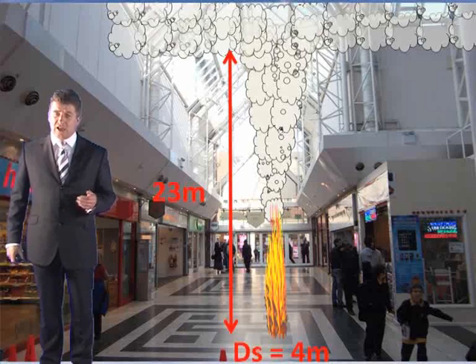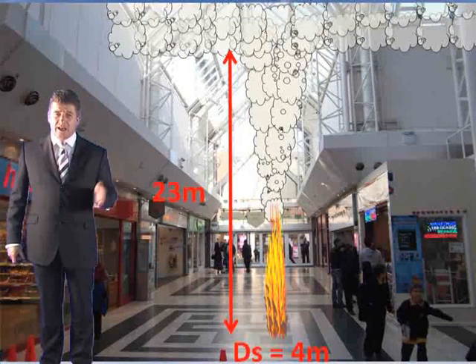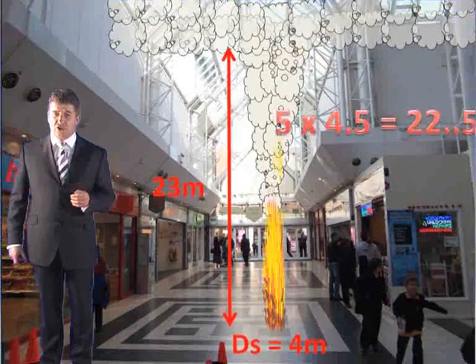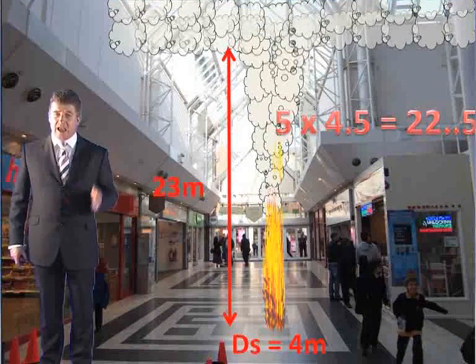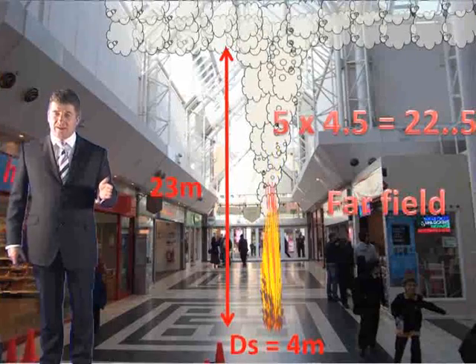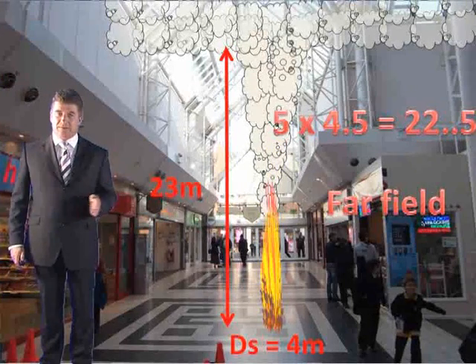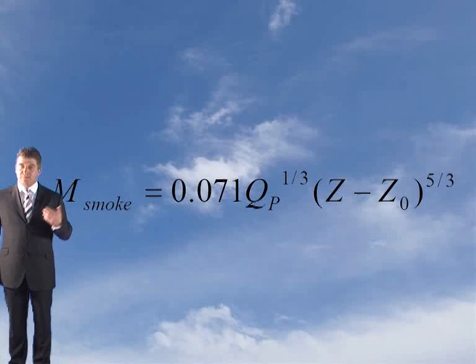In this case, the clear layer height is 23 metres. Now 5 times the longest dimension of the source is 5 times 4.5, which is 22.5. In this case, the clear layer height is greater than 5 times ds, so it's a far field model. And you'll be using this model here. This is the axisymmetric far field plume.